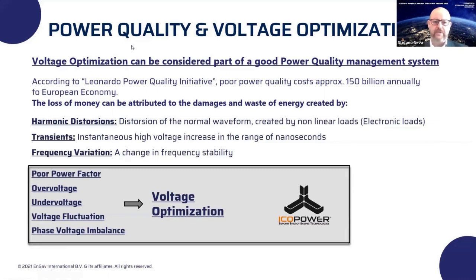Then we have other kinds of problems related to what we call transients, which are very fast high voltage increases that may lead to the rupture of motors. We have very frequent frequency variation that can change in a very short amount of time, going up and down. Then we can also have other factors related to poor power factor, overvoltage or undervoltage situations, meaning a constant state of overvoltage or undervoltage. We have voltage fluctuations of different kinds — we won't go into the details, that would take too long — or we can have some phase imbalance as a problem.